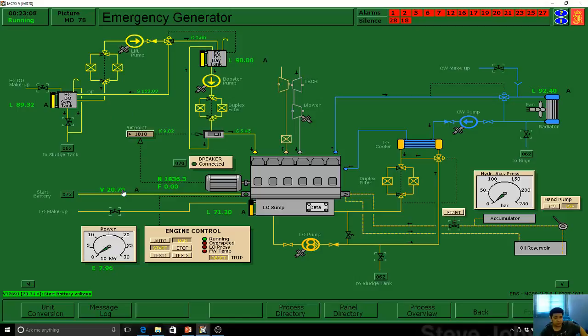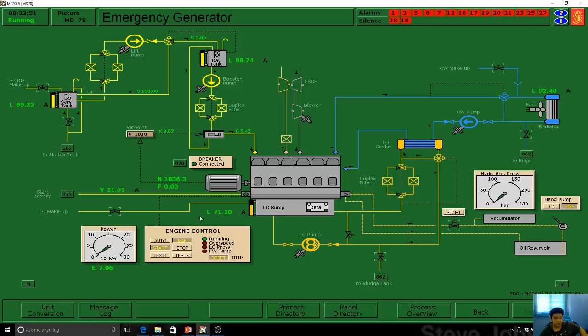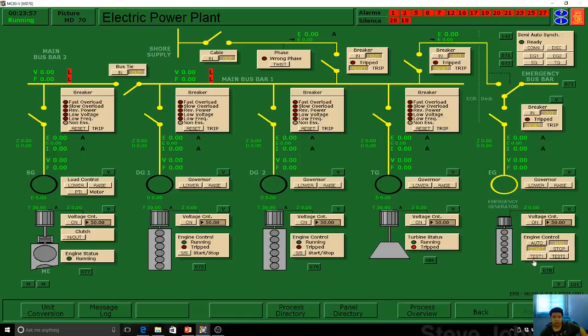Now I'm going to put power on this one and connect it to the bus bar — this is starting from cold ship condition. You can go directly to module 070. In the electrical power plant, if the indicator is black, it has not yet started; when it turns yellow, it's already started but not yet connected to the emergency bus bar. The engine control here is just the same as on the module — they have a link between module 70 and module 78. The voltage control uses excitation current to the alternator, creating electricity.